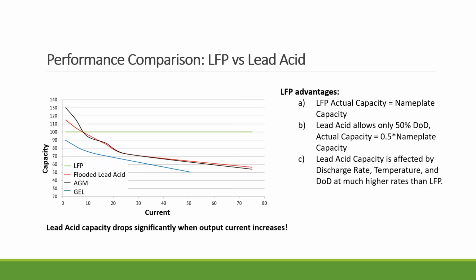So you can expect the battery to last 2 hours if it's rated for 2 hours. Also, when you design a system, if you have lead acid systems and you're going to move to lithium, it's critical to know that with lead acid the depth of discharge is only 50%, so you only get 50% of the nameplate capacity. With lithium, you can go 100%. We typically suggest either 90% or 80% depth of discharge, depending on the application. Also, lead acid capacity is affected not just by the discharging rate, but also by the temperature and the depth of discharge.